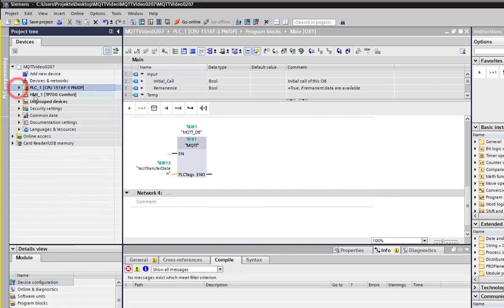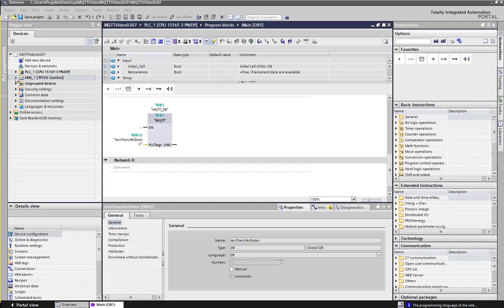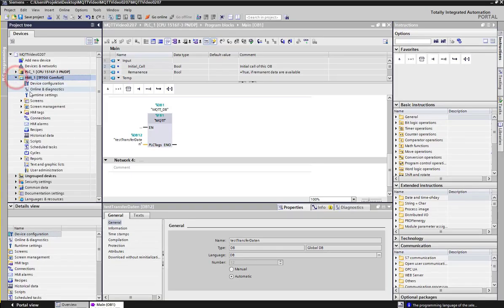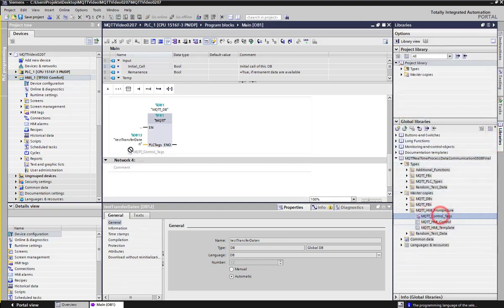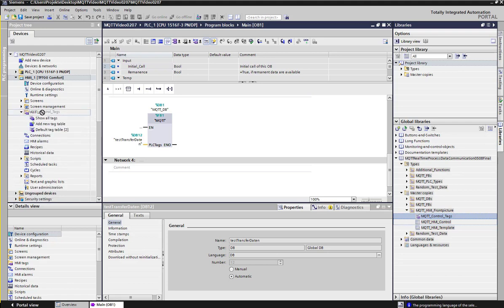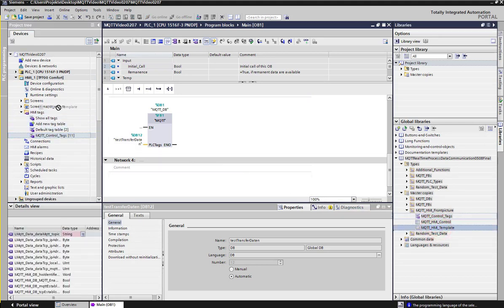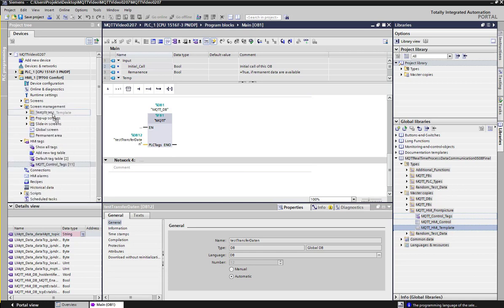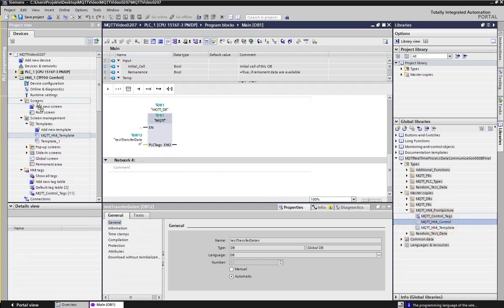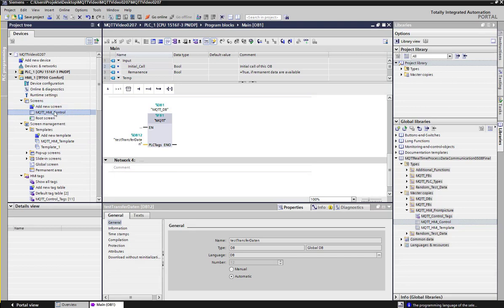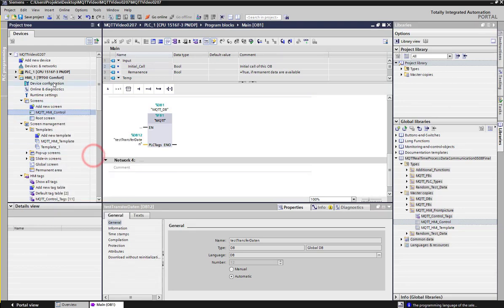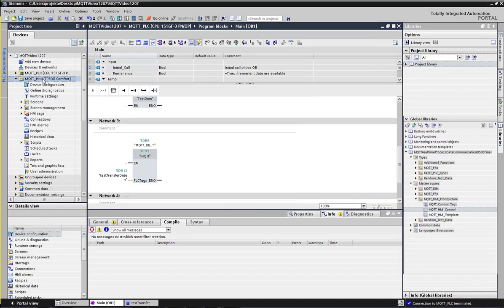Now we can set up the MQTT HMI to control the communication between the MQTT publisher and the MQTT broker. Open the HMI and drag from the library MQTT real-time process data communication in the MQTT HMI. First the template, second the front picture. Make sure the MQTT HMI picture is defined as the start screen. Compile the HMI program. Make sure there are no failures. Now we are finished.